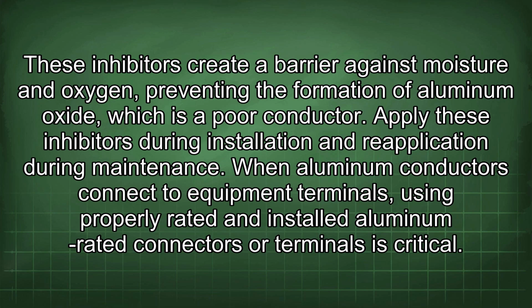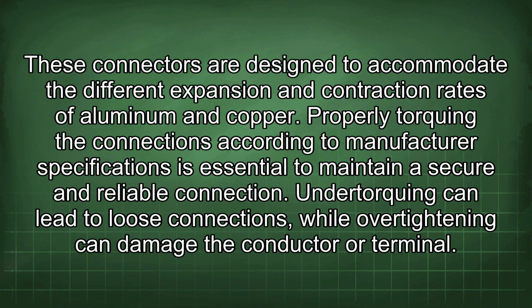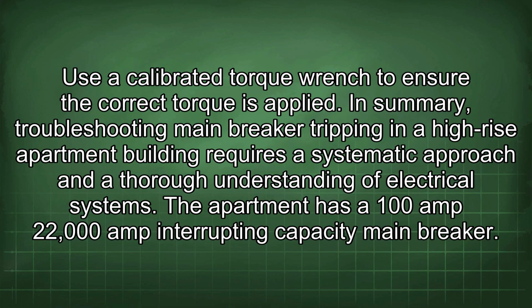When aluminum conductors connect to equipment terminals, using properly rated and installed aluminum-rated connectors or terminals is critical. These connectors are designed to accommodate the different expansion and contraction rates of aluminum and copper. Properly torquing the connections according to manufacturer specifications is essential to maintain a secure and reliable connection. Under-torquing can lead to loose connections, while over-tightening can damage the conductor or terminal. Use a calibrated torque wrench to ensure the correct torque is applied.